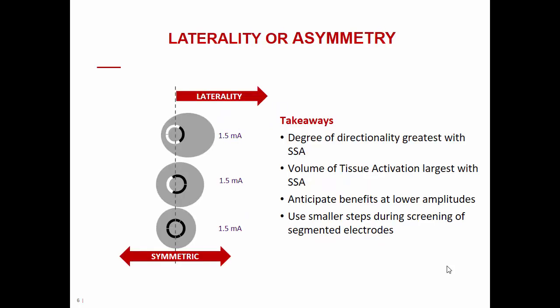Another critical concept is that activating one single segment versus activating three adjacent segments can result in very different volumes of tissue activated. When we activate one single segment, we push the entire energy — for example, 1.5 mA — into a very small surface, increasing the current density. Since current density is the main factor driving the dimension and shape of the VTA, this results in a greater VTA volume compared to distributing 1.5 mA over three electrodes, yielding approximately 0.5 mA on each.